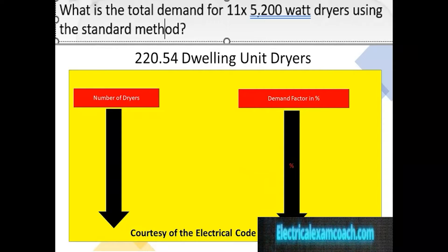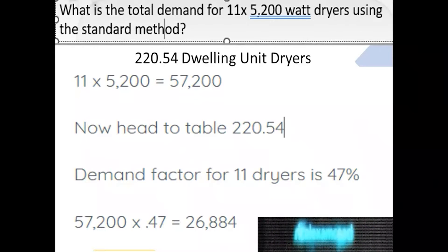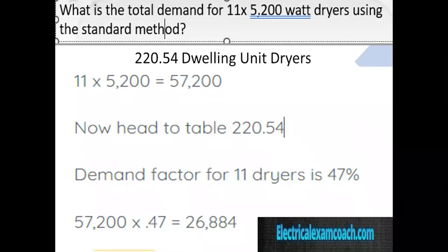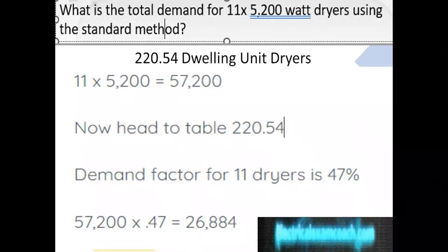For this one, we're going to start by heading to table 220.54. We start on the left-hand side and find our number of dryers, then come over and tee off with our demand factor in percentage. First, we find our total known load: 11 dryers multiplied by 5,200 each gives us 57,200. The demand factor for 11 dryers is 47%. We take our original load multiplied by our demand factor, and we get our new reduced load of 26,884.